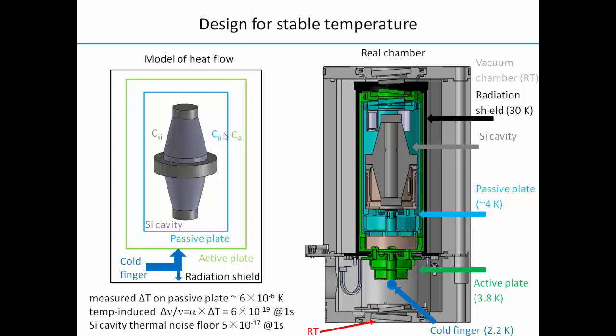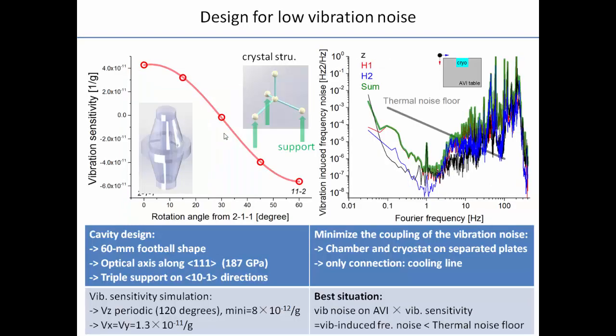Part of the cooling power from the cold finger is recycled into the radiation shield to keep it at 30 Kelvin. Since this is a closed-cycle system, vibration noise is a definite concern, which means we need to design the cavity to be vibration-immune.